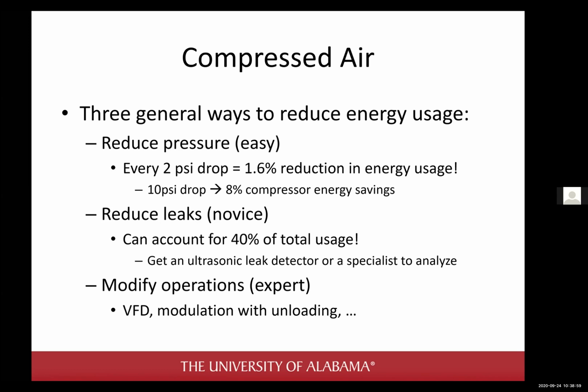Anyway, I'm not here to bash anybody on poor usage of compressed air. I'm here to tell you how to increase your efficiency. So reducing pressure is easy, leaks maybe more difficult. And you can never really totally eliminate leaks, right? You can only slow them down. So you just have to be vigilant. You have to be on top of things. Anyway, more expert levels of reducing compressed air energy usage, which can actually yield a lot of savings, are looking at the specifics of how you're operating things. It says VFD modulation with unloading. Those are just control strategies on the compressor, and sometimes using a different control strategy can really be beneficial.